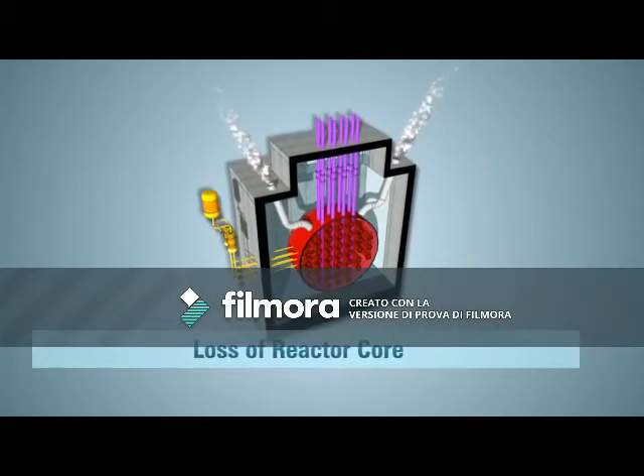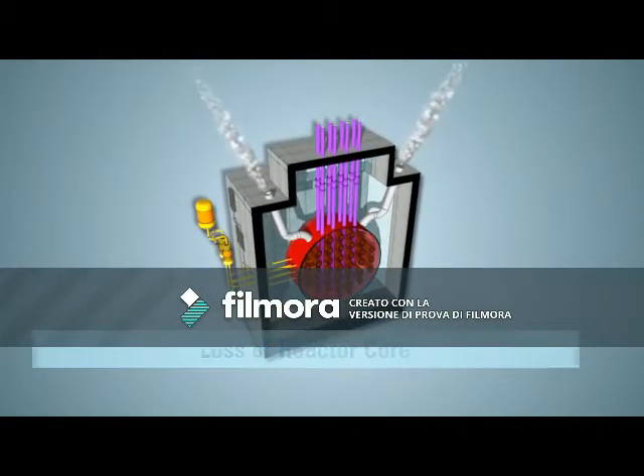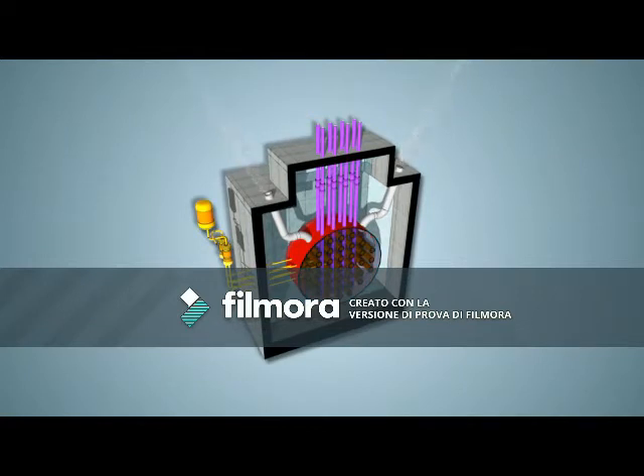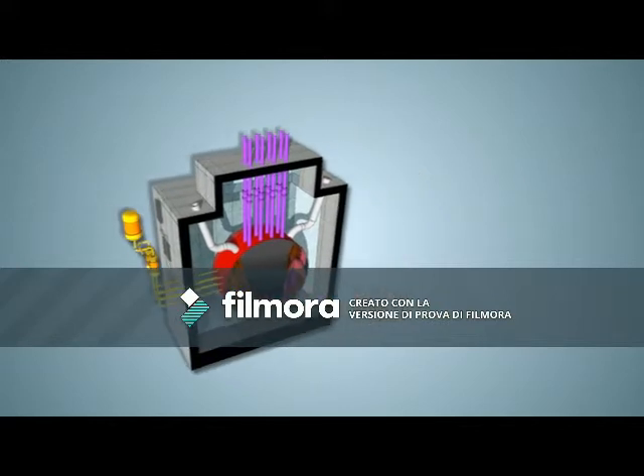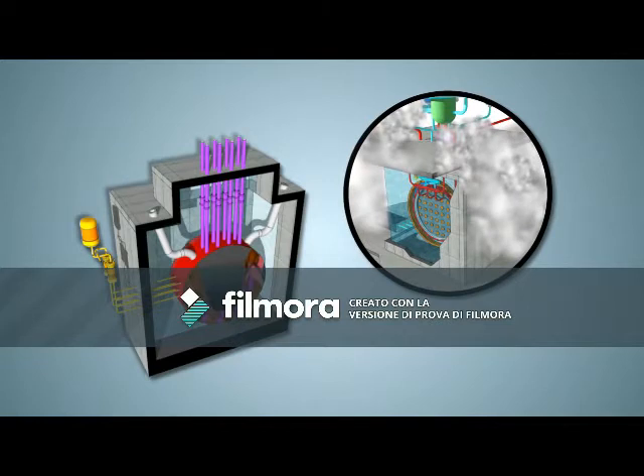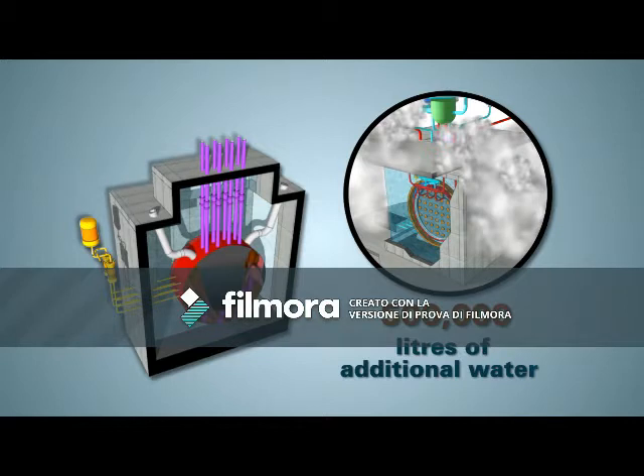Assuming the accident is not stopped, all remaining heavy water evaporates. The exposed fuel begins to melt and the reactor core starts to collapse inside the calandria. The vault that holds the calandria also holds about 500,000 liters of additional water. That water now starts to heat up.